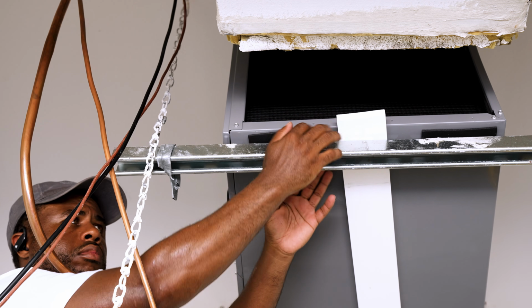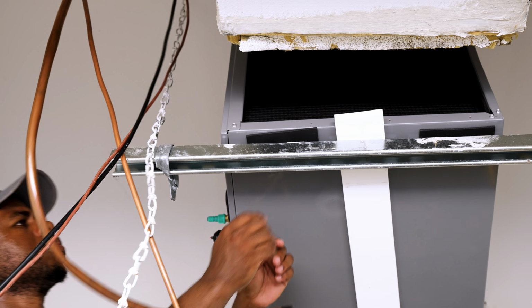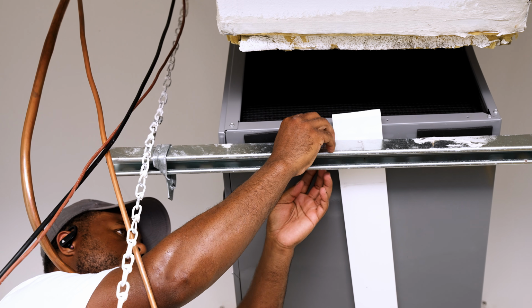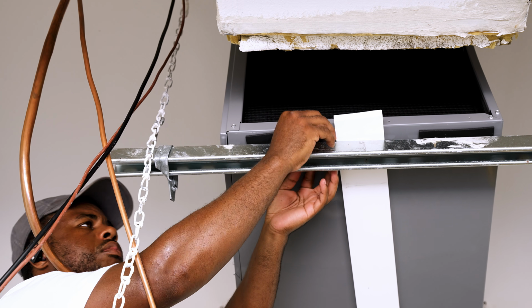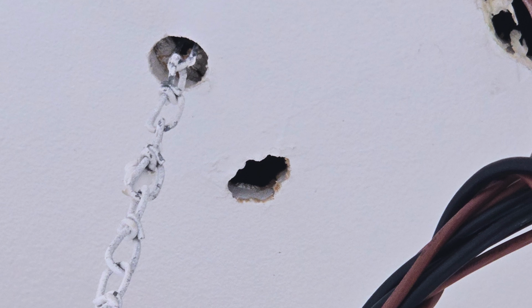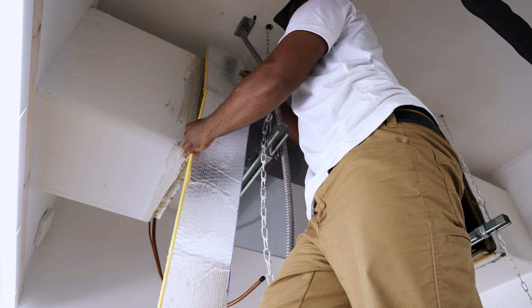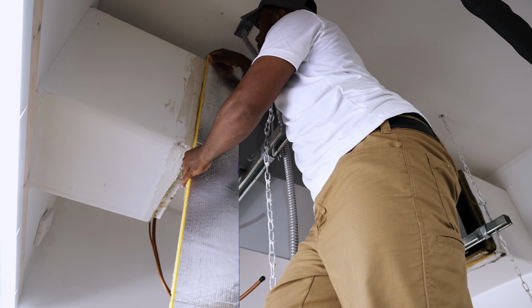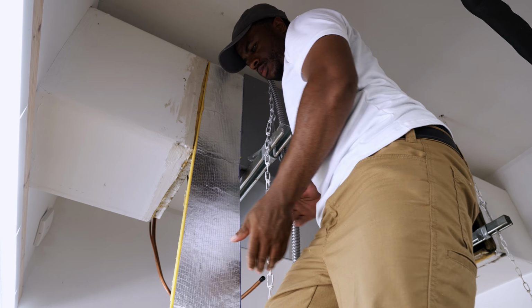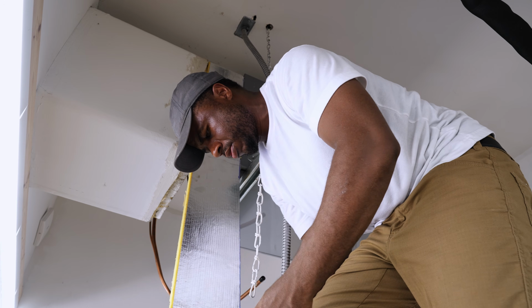One thing I wanted to note is I made sure the chain and everything was leveled before I put the unit in place. Since the new air handler was a little shorter, I ended up moving the chain about 3 inches. Now I took the duct board that I made earlier, measured all 4 sides, and cut the ductwork accordingly to fill the gap.